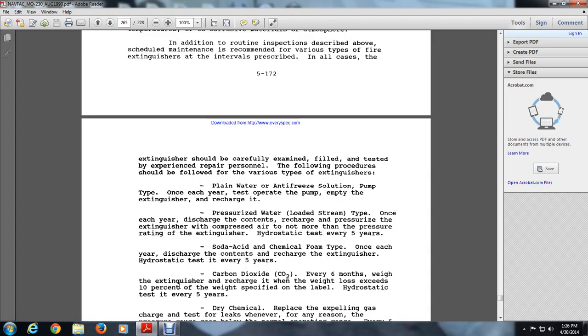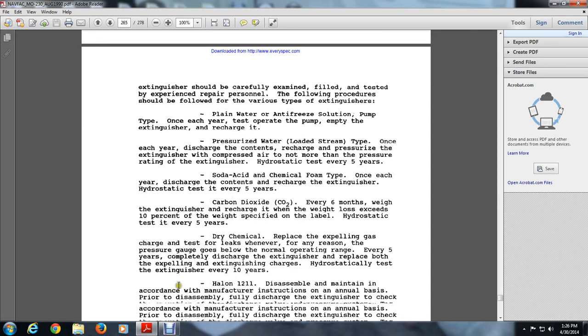Carbon dioxide, every 6 months: weigh the extinguisher and recharge if the weight loss exceeds 10% of the weight specified on the label. Hydrostatic test every 5 years. Dry chemical: replace the expelling gas, and test for leakage, or whenever the pressure gauge is below the normal operating range, every 5 years. Completely discharge the extinguisher, replace both the expelling gas and the extinguisher charge, and hydrostatically test the extinguisher every 10 years.